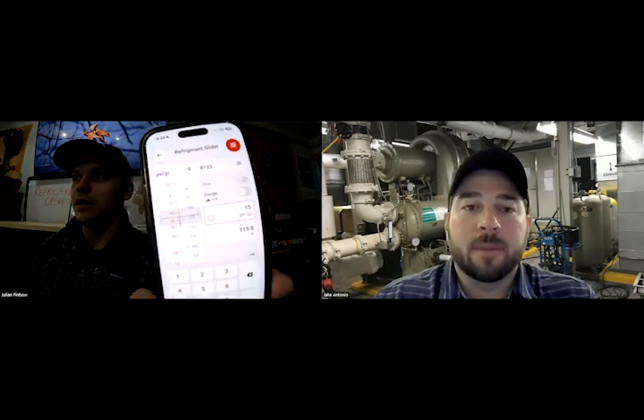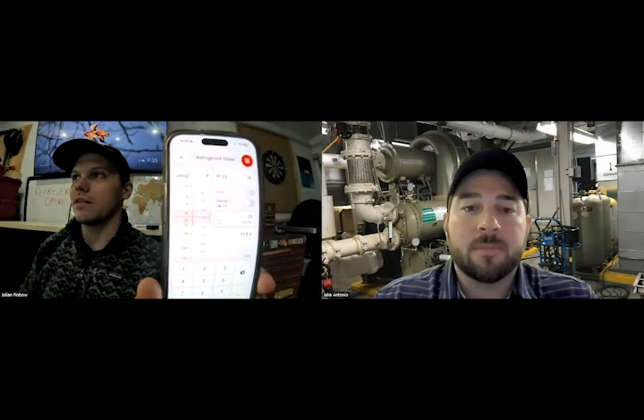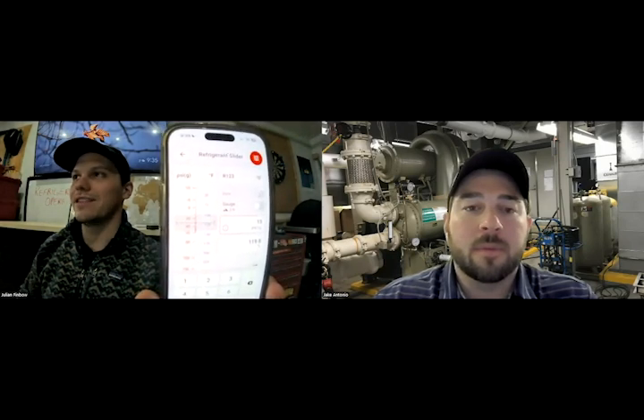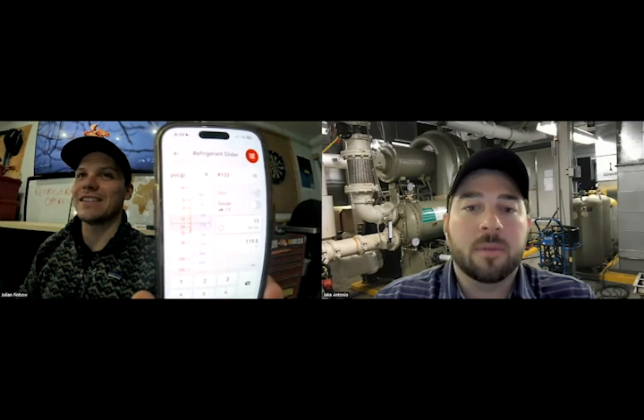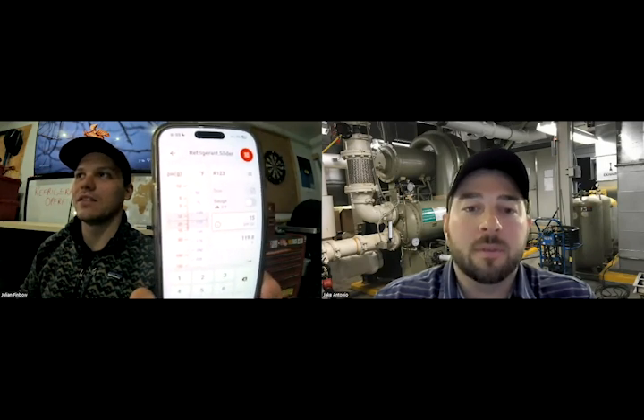Different industries, right? If you think about a normal pressure test on a small system, you're thinking 134A, R22, 410A, high pressure tests. But in the chiller world and even the industrial world, it's a little bit different. There's other things to be considered. Yeah, that's cool. We talked about this in a previous episode, R123, but I had to look that up. I mean, not ideal, I should be sharing my screen, but I don't think this is mirrored, the Ref Tools app by Danfoss, that's hilarious. That's a saturated condensing temperature of 120 degrees at 15 psig. So yeah, it's a very low pressure refrigerant.